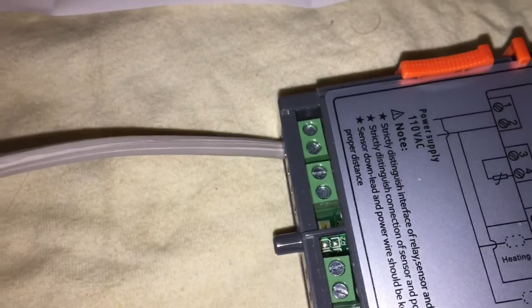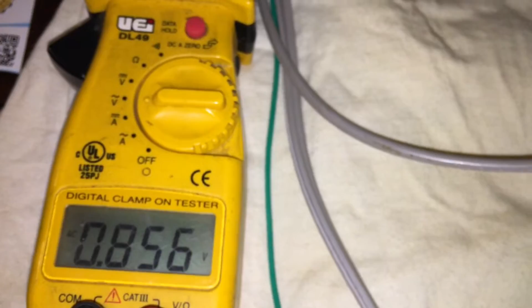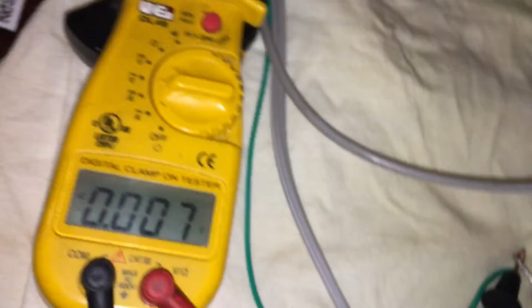I'm putting my line, which is correct, to number 1. This is what you'd get if you put it to the neutral instead, you get nothing. And there's nothing on that wire there. So this is your hot wire right here, 120 volts between this wire and ground. That's your hot.